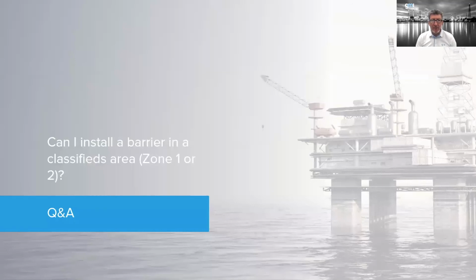There was a live question here that I should have answered earlier. It says, how does an isolation barrier allow HART signal? Well, we looked at the transformer. The transformer has a secondary circuit in there to transfer HART. So there's a dedicated isolation circuit for HART that is capable of transferring I don't know how many kilohertz, 4 or 5 kilohertz, if I remember correctly. The superimposed signal. You need to design a transformer to read it.